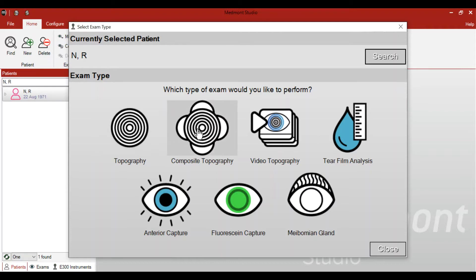When you require a larger view of the cornea — when you would like limbus-to-limbus data, or when you are building a specialty corneal GP or scleral lens — you will choose a composite topography. Anytime you want a lot more information on the cornea, including the peripheral cornea all the way around for limbus-to-limbus coverage, the composite topography strings five different fixations together to create the larger view of the eye.